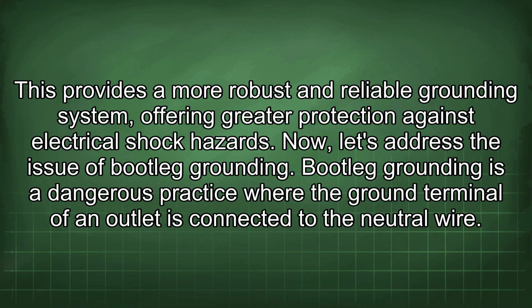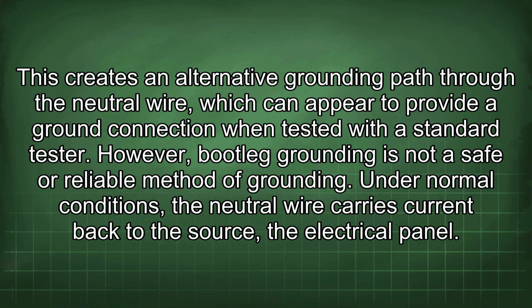Now, let's address the issue of bootleg grounding. Bootleg grounding is a dangerous practice where the ground terminal of an outlet is connected to the neutral wire. This creates an alternative grounding path through the neutral wire, which can appear to provide a ground connection when tested with a standard tester. However, bootleg grounding is not a safe or reliable method of grounding.